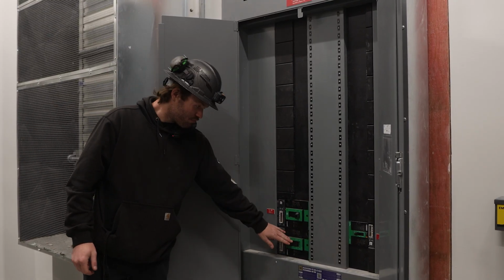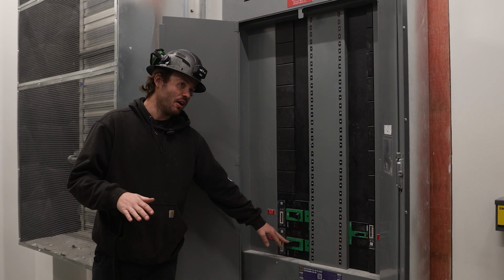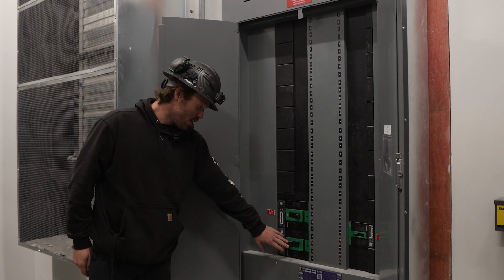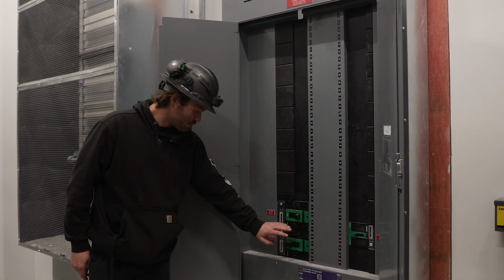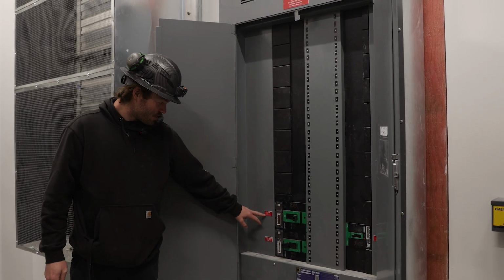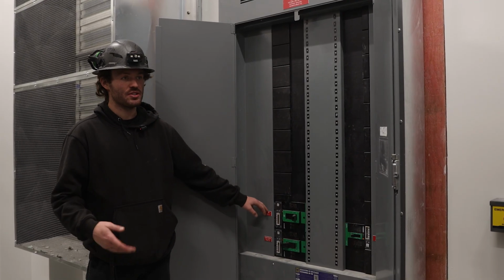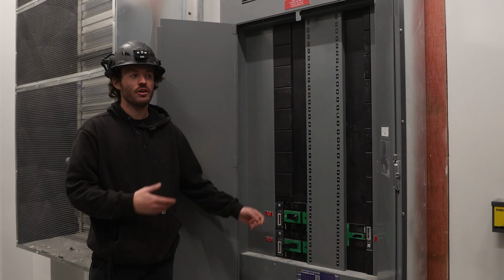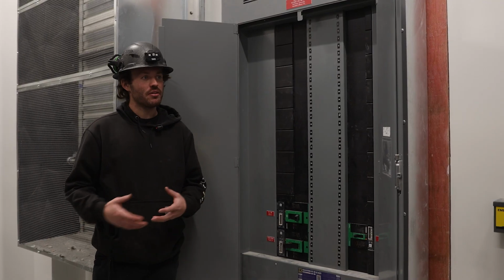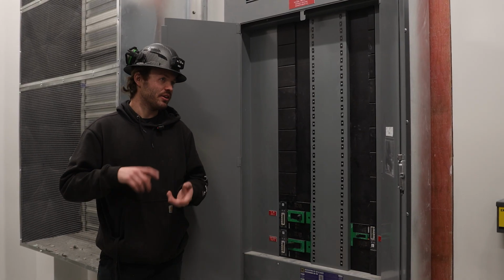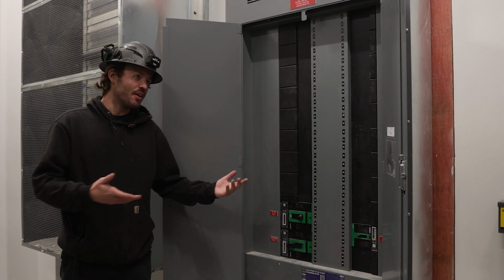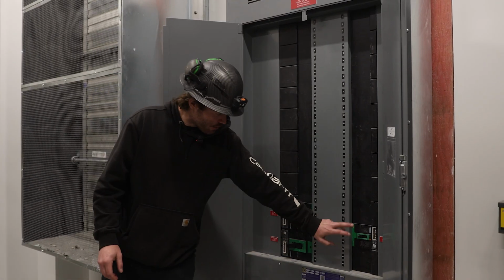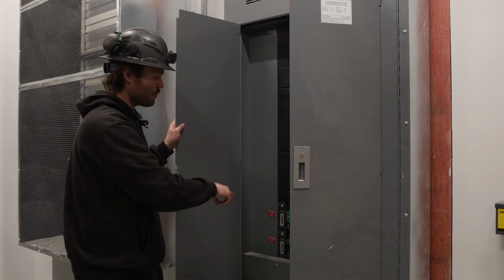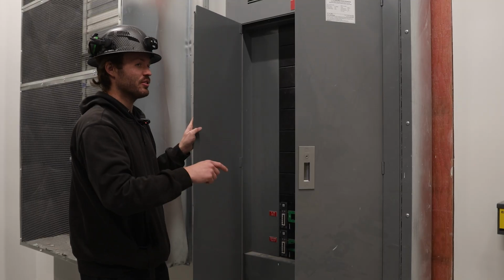So this guy pretty much entirely can be left off. If it's on, you can flip it off. Keep it off. Above that is our transfer switch emergency. That's the transfer switch that I'll be going over. It's the one that you'll be testing with, and that's the one that does the elevator, the lights, everything other than the fire pump. The fire pump has its own breaker. So fire pump and transfer switch emergency, those breakers always on.